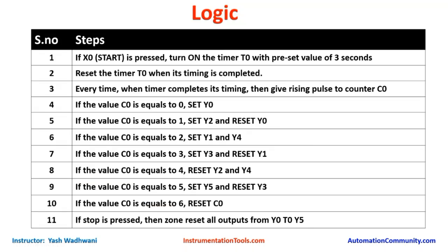Now let us understand the logic required to create this project. If the start button is pressed we turn on timer T0 with a preset value of three seconds, because we want three seconds of delay between each operation. It will count up to three seconds and when the timer value reaches three seconds, the T0 bit will become on and reset itself so it can restart counting from zero. When this bit becomes high, we give a rising pulse to our counter. Initially the value of C0 will be 0, and if the counter value equals 0 we set Y0 so cylinder 1 will advance.